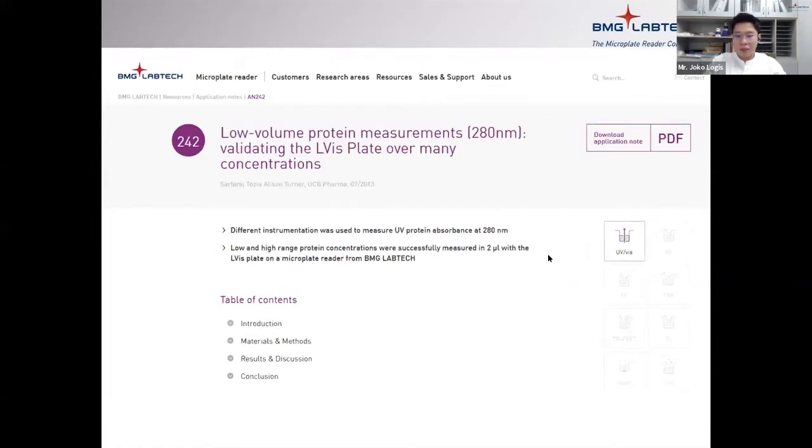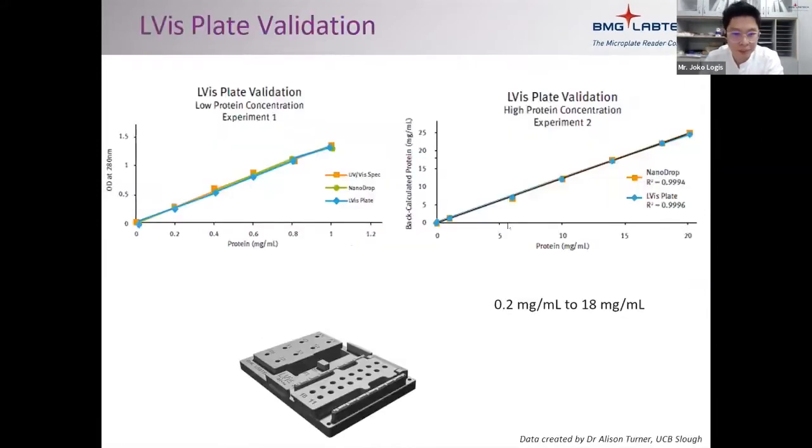You can also do low-volume or micro-volume protein measurements using our accessory, the LVis plate. You use just 2 microliters of your protein sample. Our LVis plate has been validated across a range from 0.2 mg/mL to 18 mg/mL protein concentration. We have also compared its performance with conventional UV spectrophotometers and Nanodrop, and the performance is very similar.